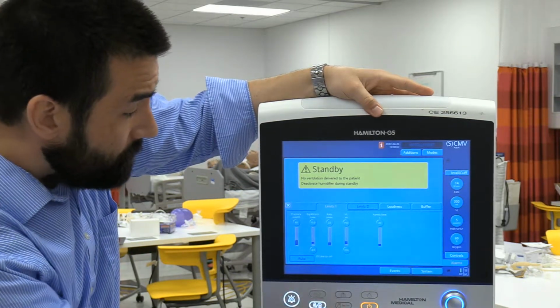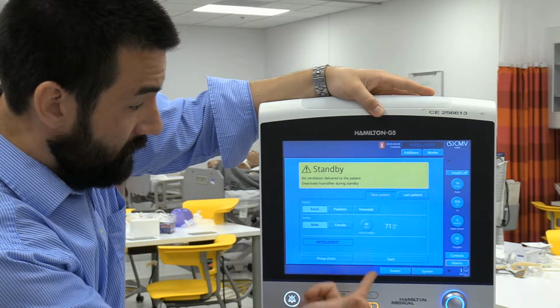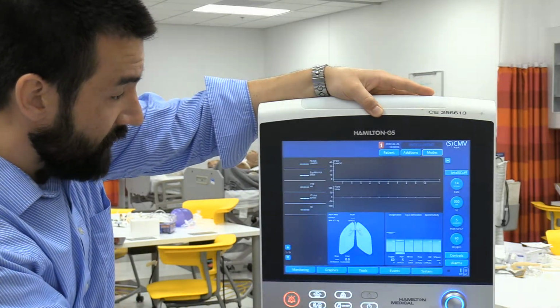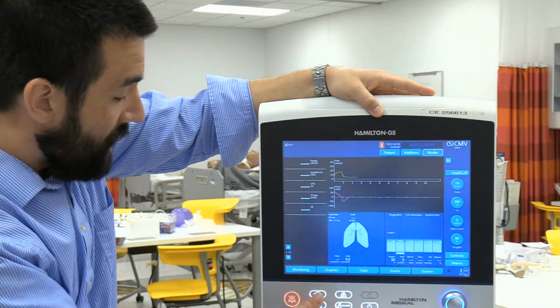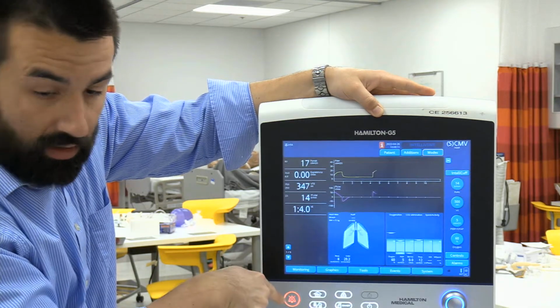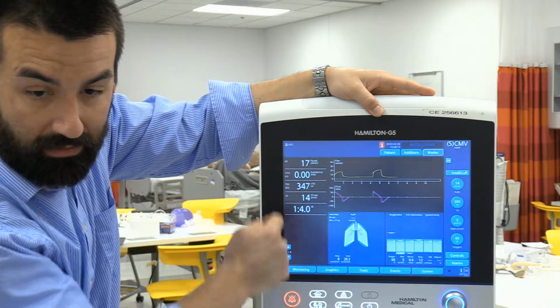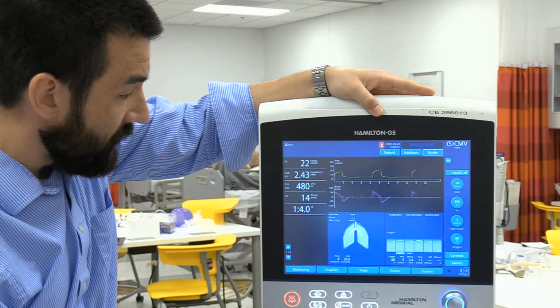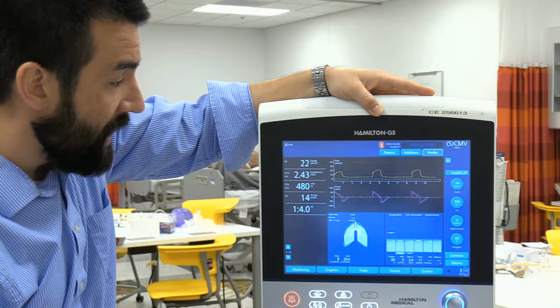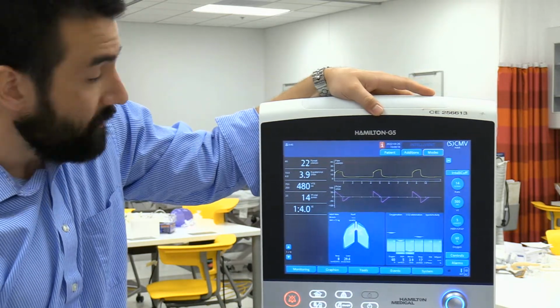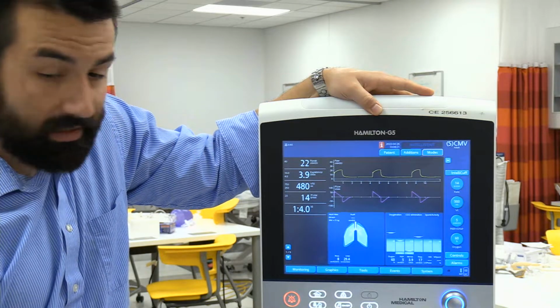So at this point, that looks pretty good. If I was liking it, I could go ahead and hit start ventilation. I do like to point out that the Hamilton vent is going to pre-silence your alarms for 1 minute. You can see that countdown up here. A lot of our values, like our exhaled minute volume and things like that, are not going to be reached, so it's going to start honking at you right from the get-go. So I do like that it does this.